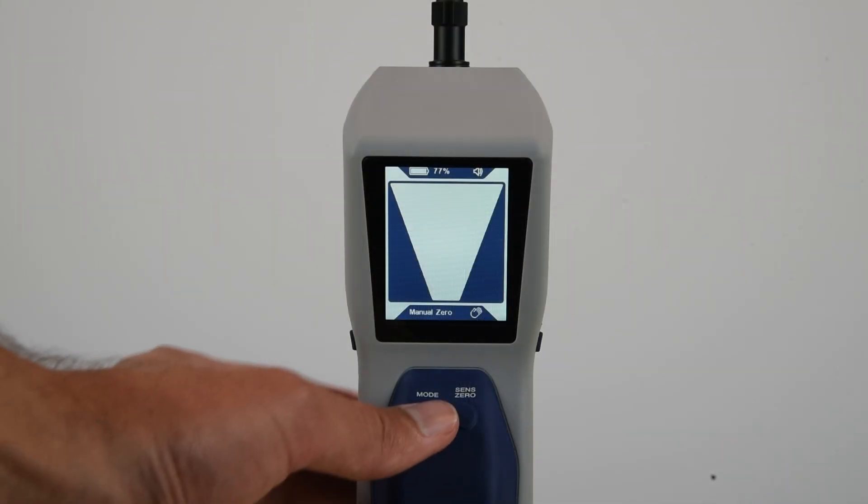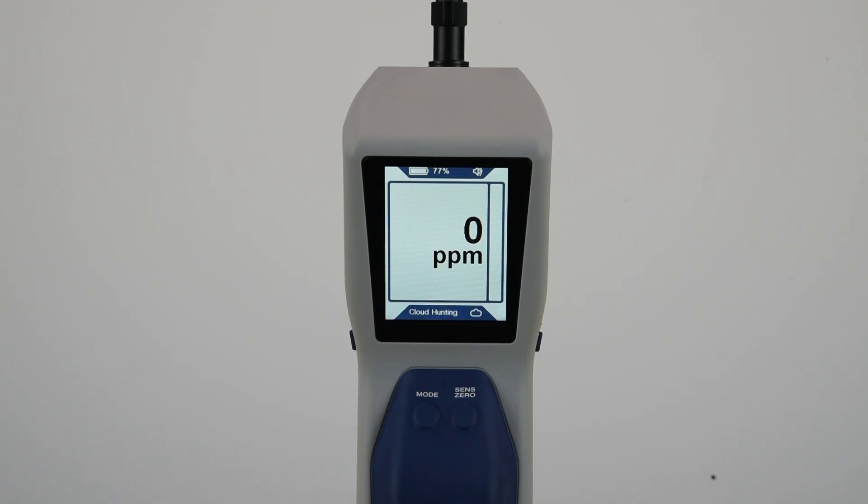When your DTEK Stratus is not detecting refrigerant in cloud hunting mode, listen for the pump and the ticking sound. If you don't hear the pump, bring the tool back to the distributor for assistance with the repair process.